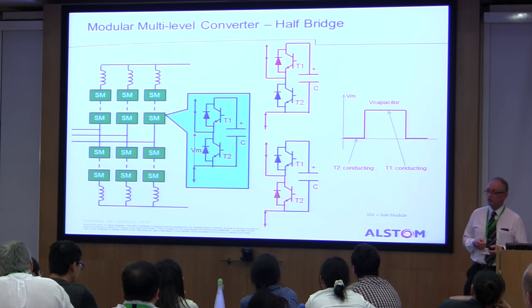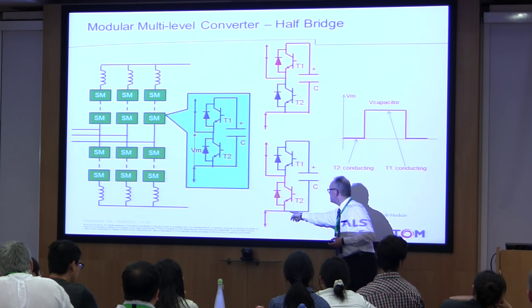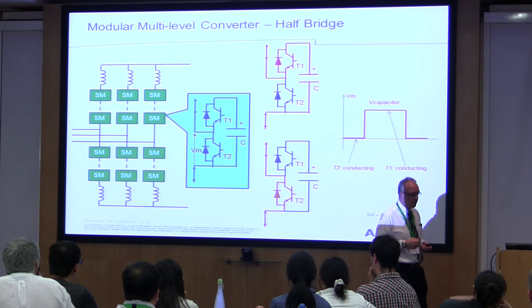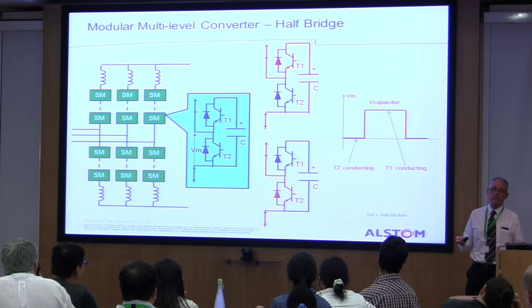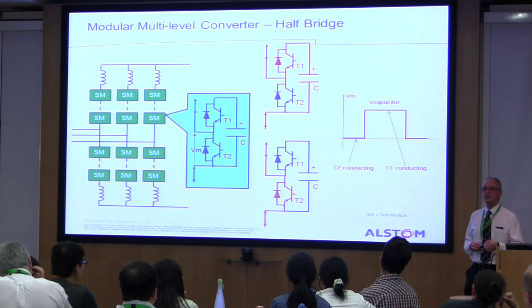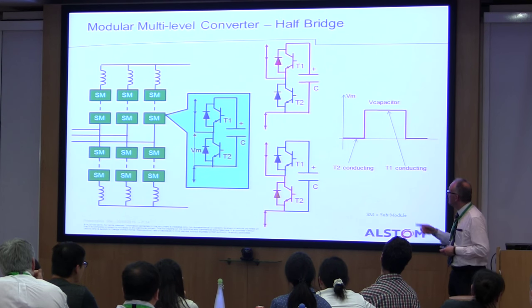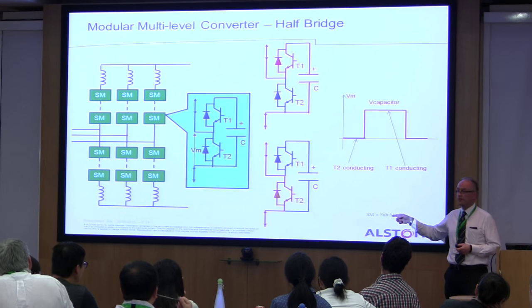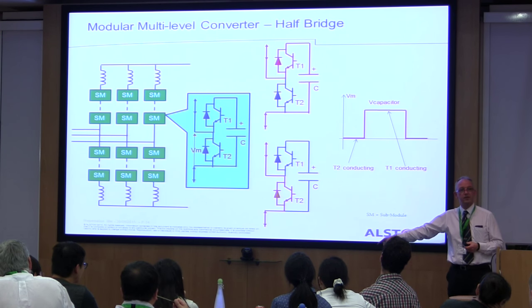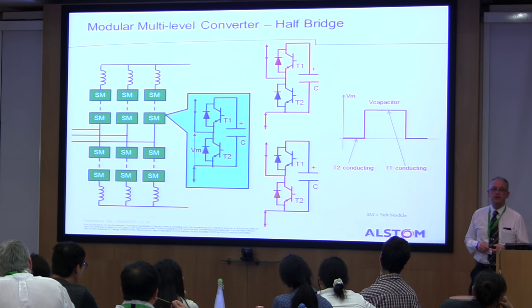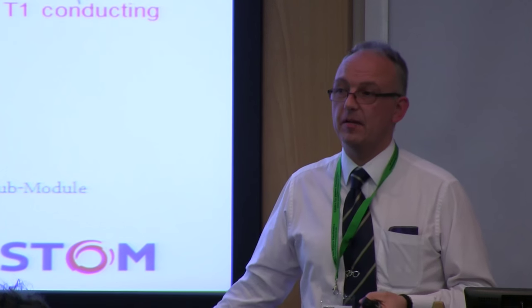The disadvantage of the half-bridge submodule compared with the full bridge is the diode — because if we get a fault on the DC side, I can't stop the current. With a thyristor valve I could remove firing pulses at the next current zero and the thyristor would turn off, electronically interrupting fault current. But with a diode in each submodule circuit, if there's a DC-side fault, the primary protection must be the AC breaker. From a European perspective, where most schemes are point-to-point cable, if you've got a cable fault it'll take days, weeks, or even months to repair for a submarine cable — so tripping the AC breaker may not be that bad a thing.